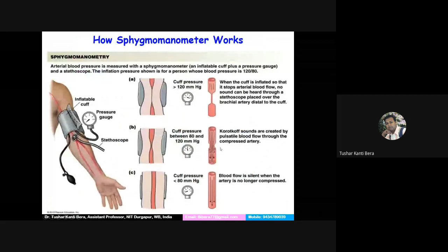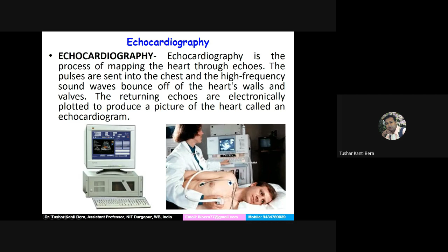And ultrasound, I have already explained, is generated by an electronic machine, which will have a monitor also. That machine will send an electric pulse, which will be converted into mechanical vibration at very high frequency, generating sounds which cannot be heard by the human ear. That sound will travel to the tissue and be reflected back. Again, the sensors will receive that sound, and the sound will be converted to an electric signal, and the electrical signal will go to the computer again. The applied signal and the received signal will be compared, and the image will be created by the algorithm.